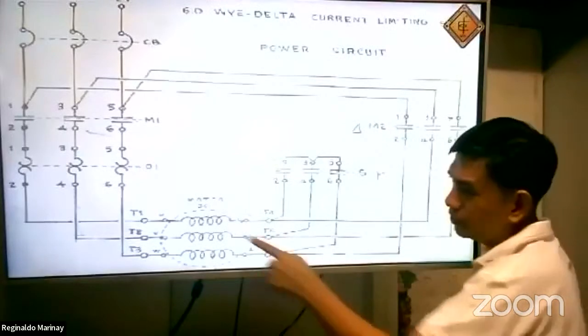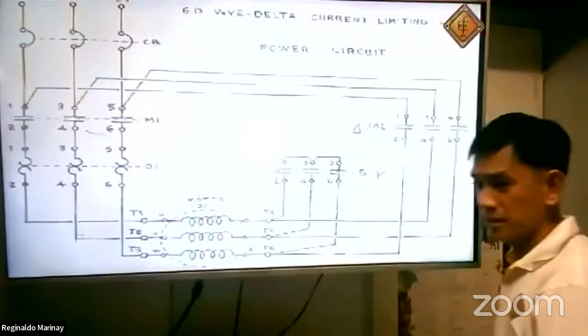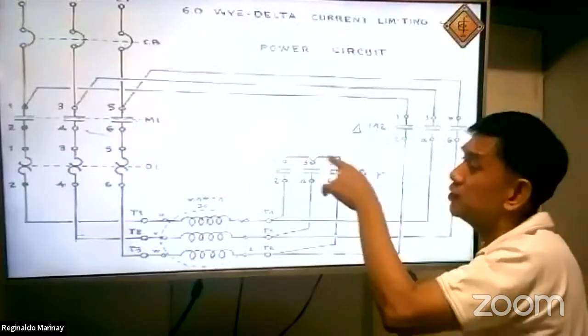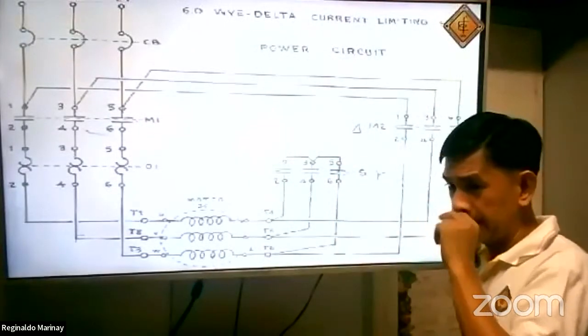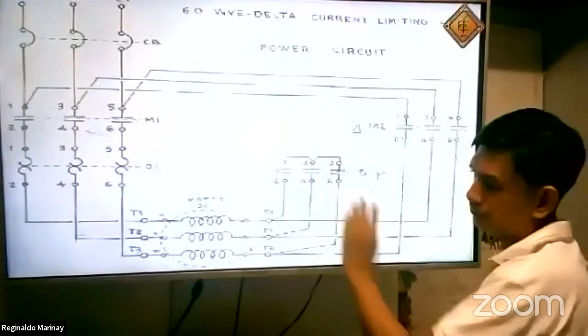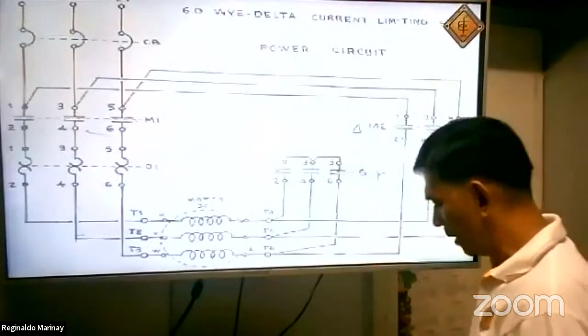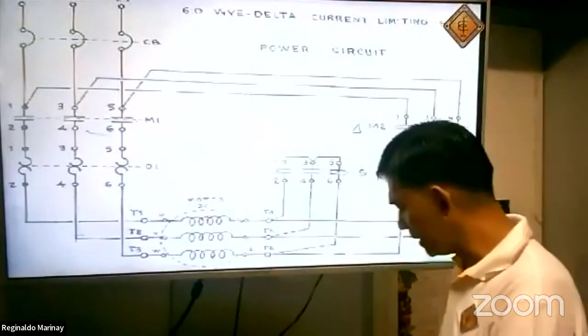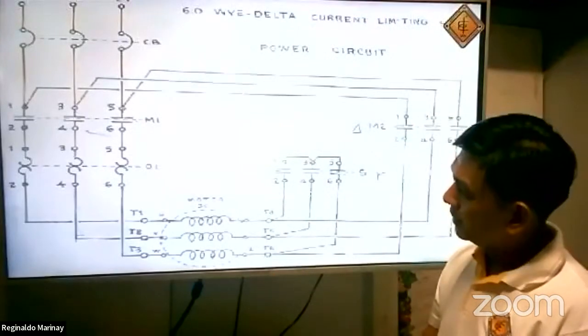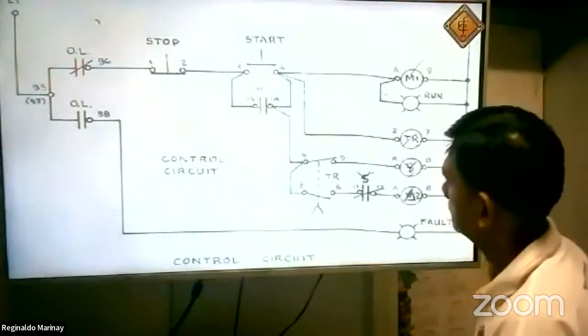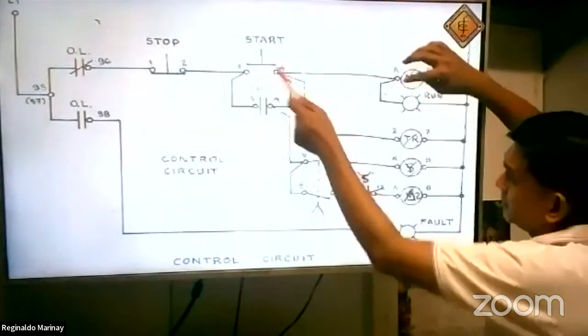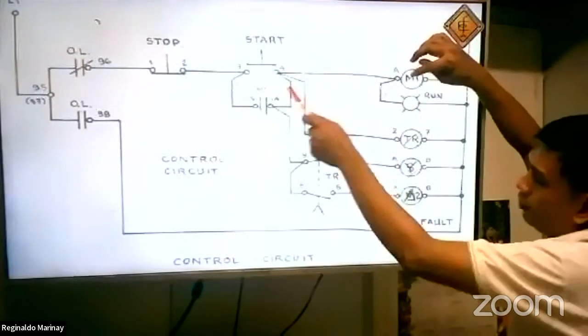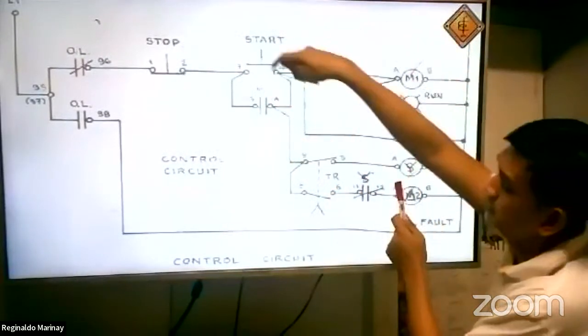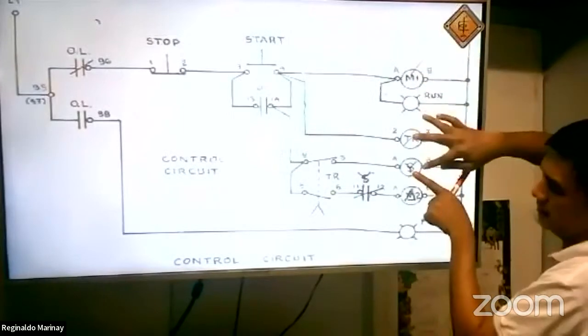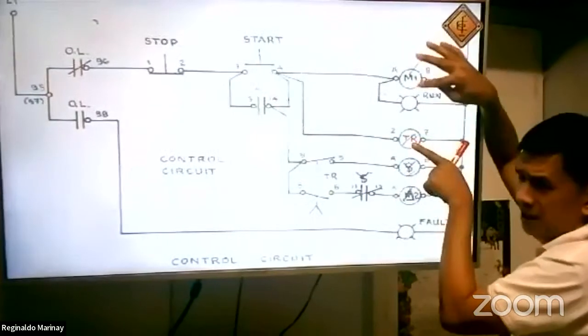So, the connection of these three windings is connected in Y. This serves as the neutral of the motor. That is the neutral. Now, what will happen when you reach 3 seconds? Take a look again at our control circuit. Remember, this coil becomes energized once you press the start button. The timing relay becomes energized.